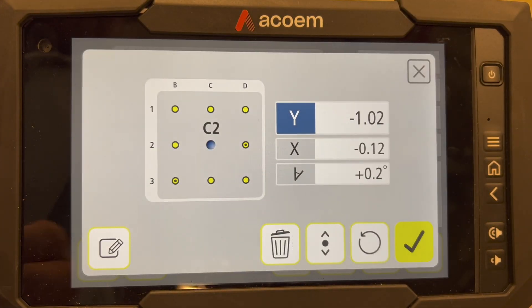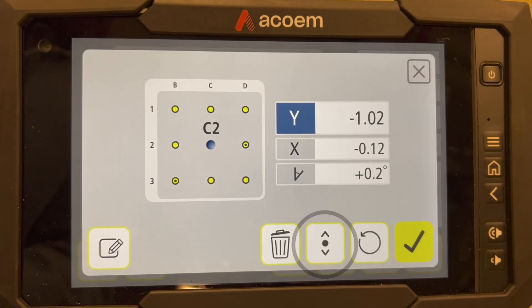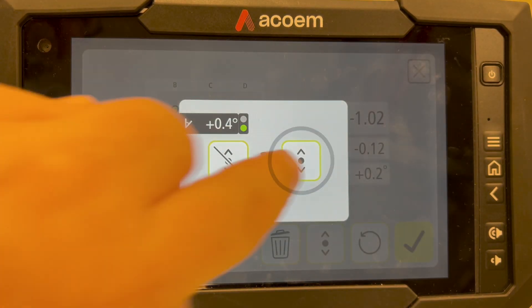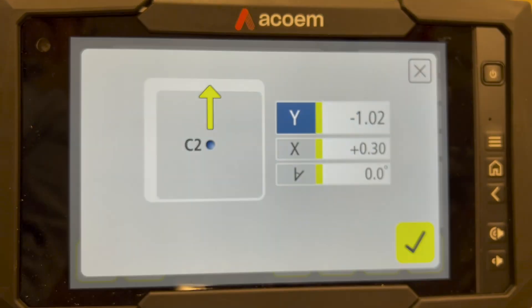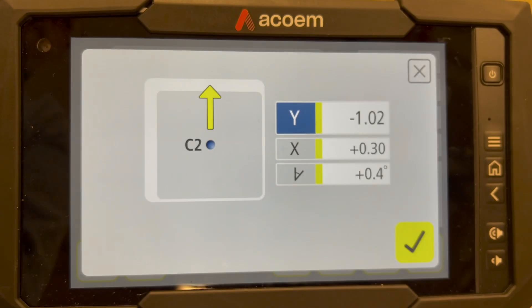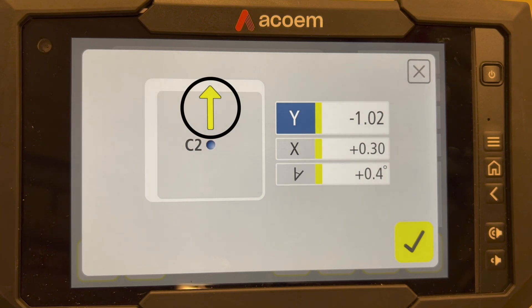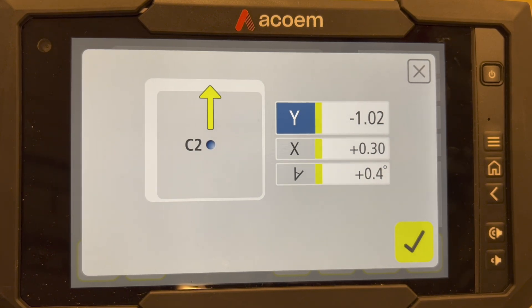The adjustment icon will now show when we go back to adjust C2. Press the adjustment icon. The value to be recorded is shown in Y. The arrow depicts which direction to adjust. Y equals the thickness of shims needed.